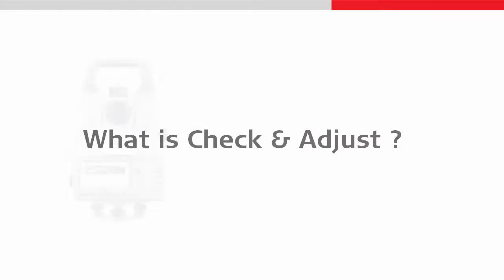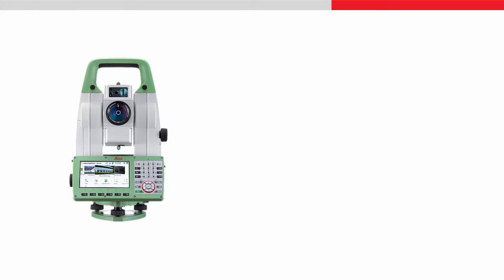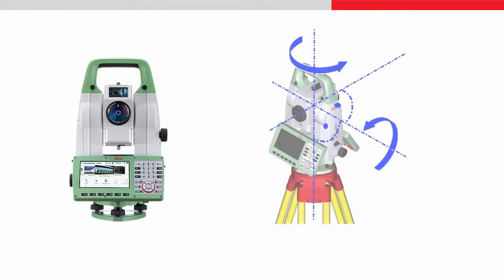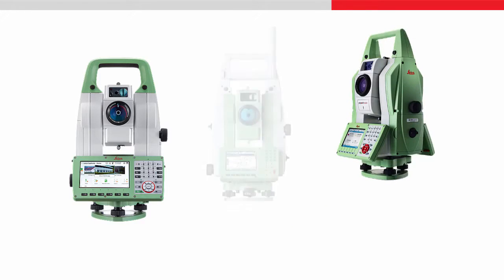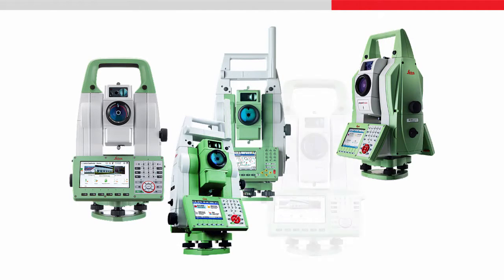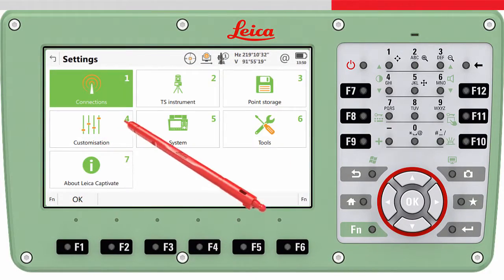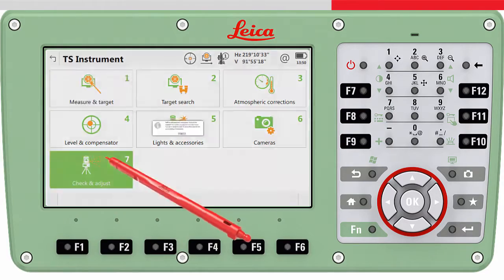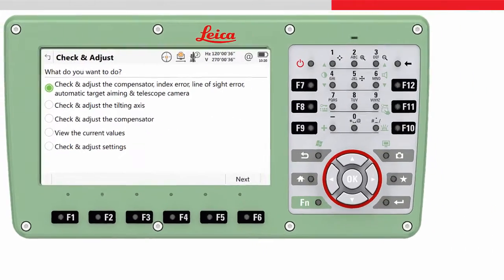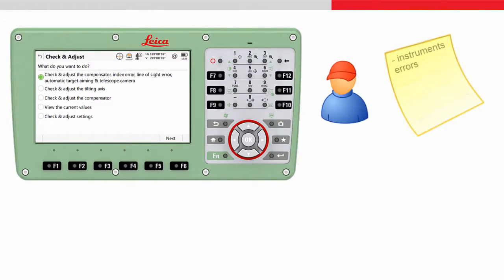As previously mentioned, a total station has to fulfill specific requirements. Unconsidered misalignments of the rotational axis can lead to wrong results. The check and adjust tool can be found in all currently available Leica Total Stations and Multi-Stations, in Settings, TS Instrument, and Check and Adjust. The tool allows the user to determine the typical instrument errors as well as misalignments of the automatic target aiming and the crosshair of the telescope camera in an easy and fast way.